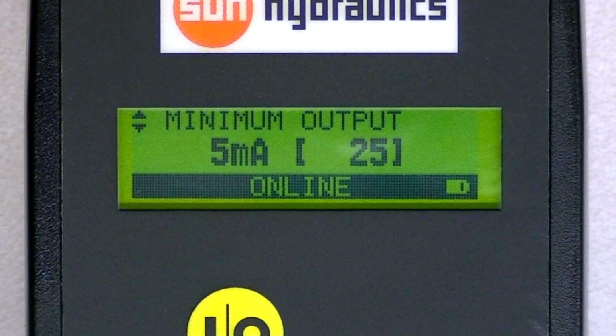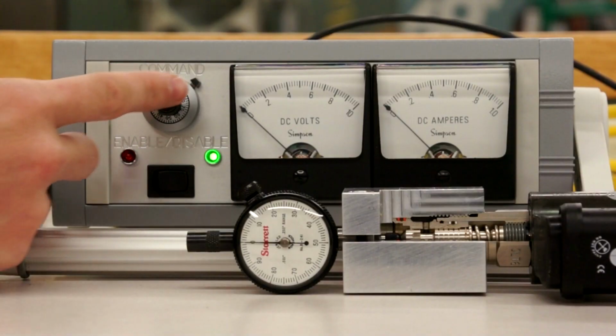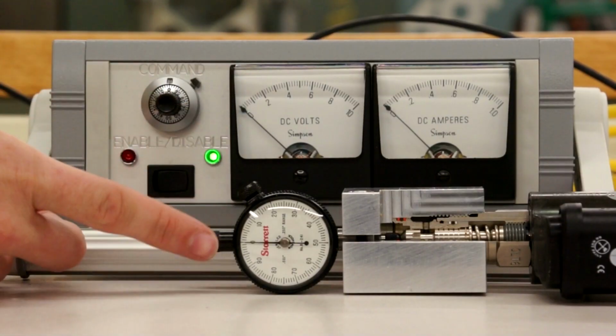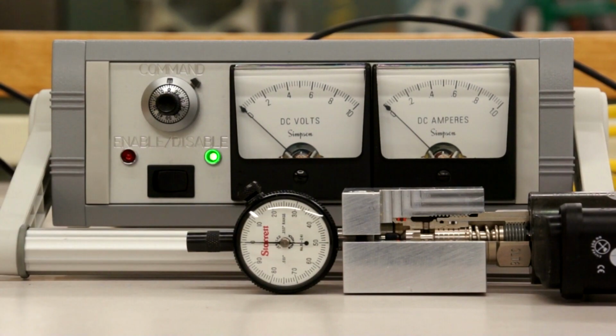Our minimum output is 5 milliamps, so at 0 volts input, we're outputting a minimum current of 5 milliamps. Our maximum output is 590 milliamps. That will be the current being output from the amplifier at 10 volts input command. Next, we'll sweep the input from 0 to 10 volts to show the valve position changing proportionally.